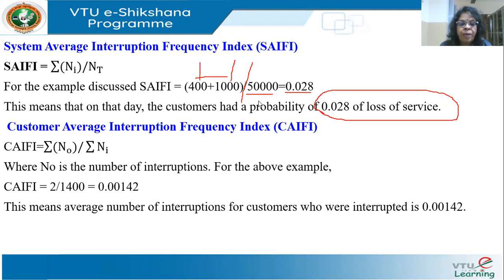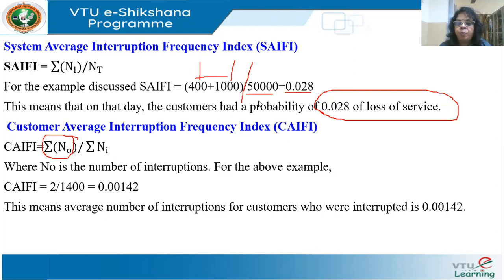The Customer Average Interruption Frequency Index (CAIFI) is the number of interruptions No divided by the number of affected customers. For the above example, there were two interruptions affecting 1,400 customers totally, so it is 0.00142 — meaning around 0.1% of the customers were affected. These four indices — SAIDI, CAIDI, SAIFI, and CAIFI — are very commonly used in reliability for distribution systems.